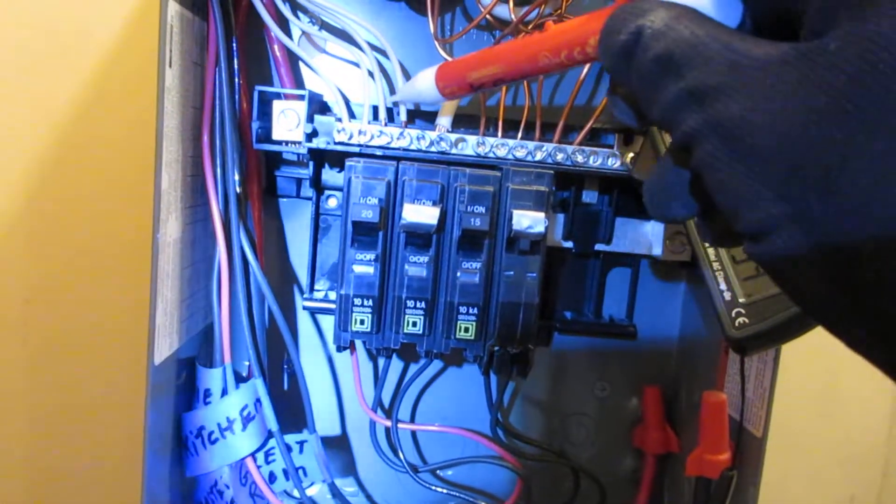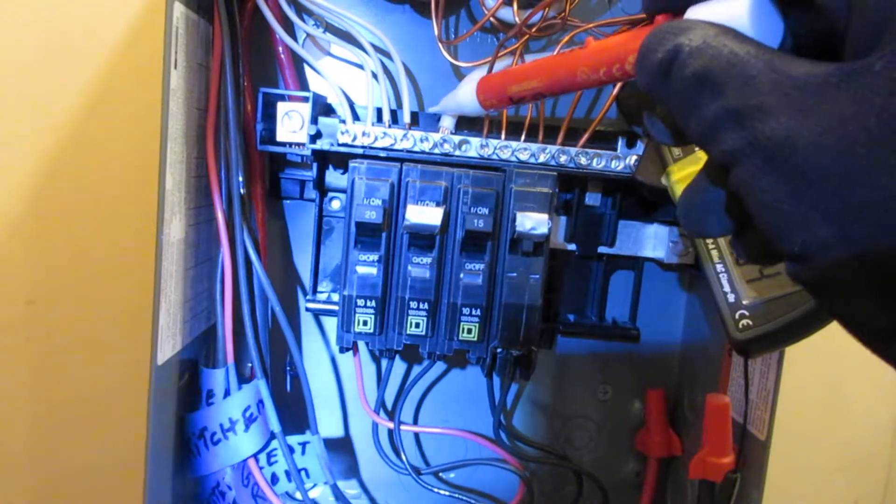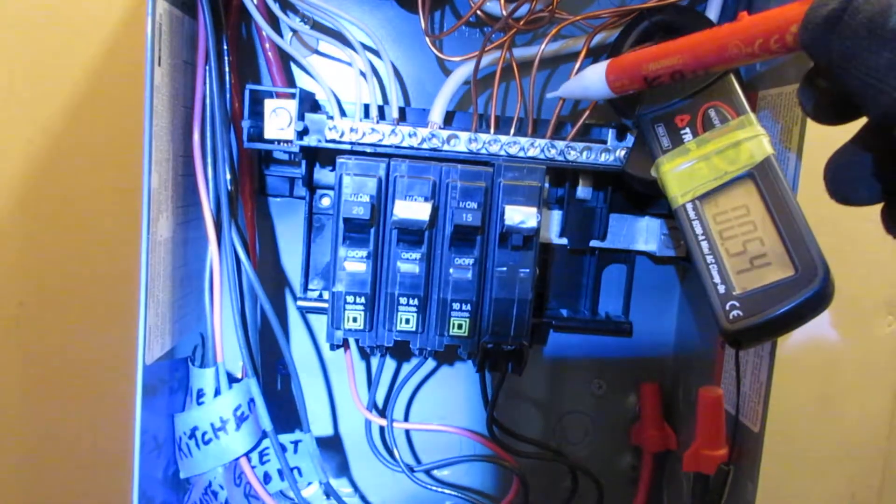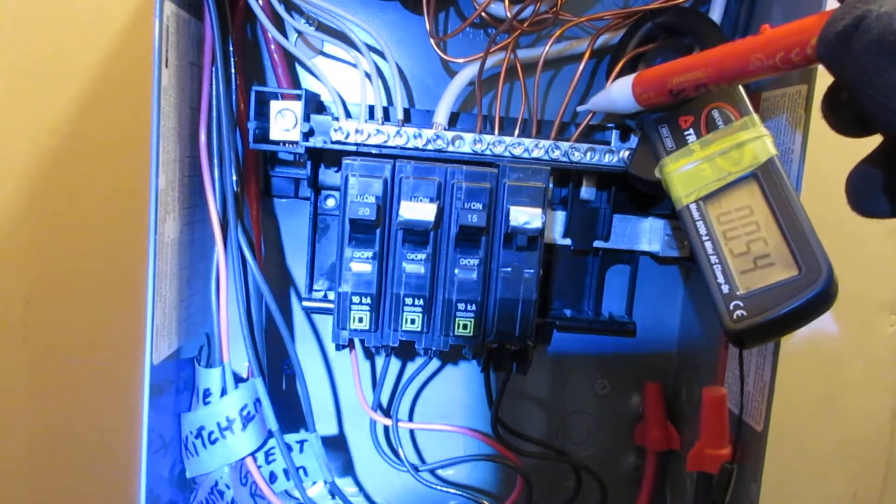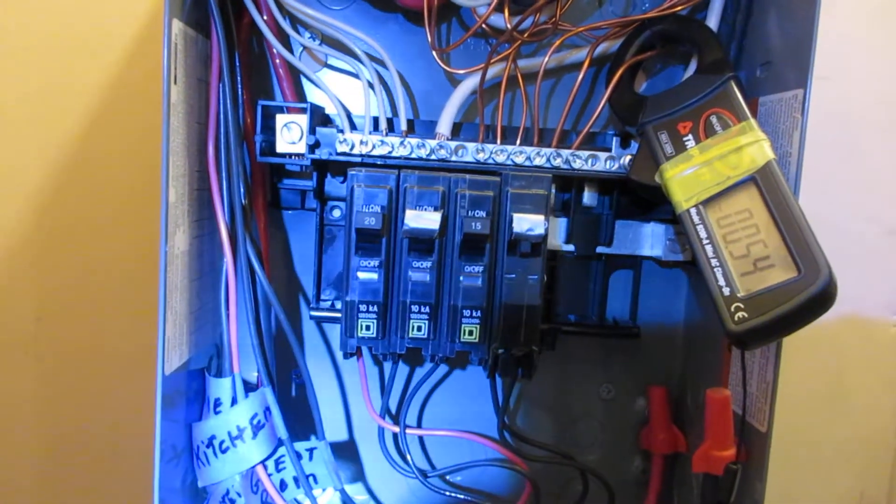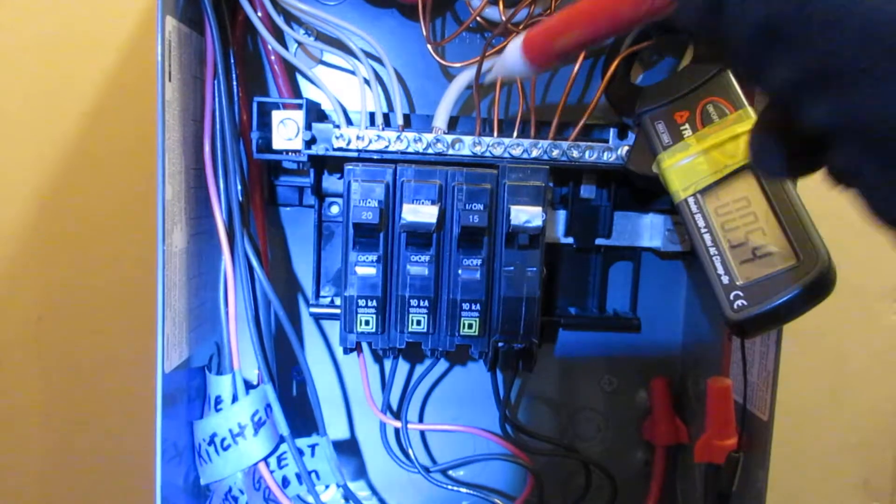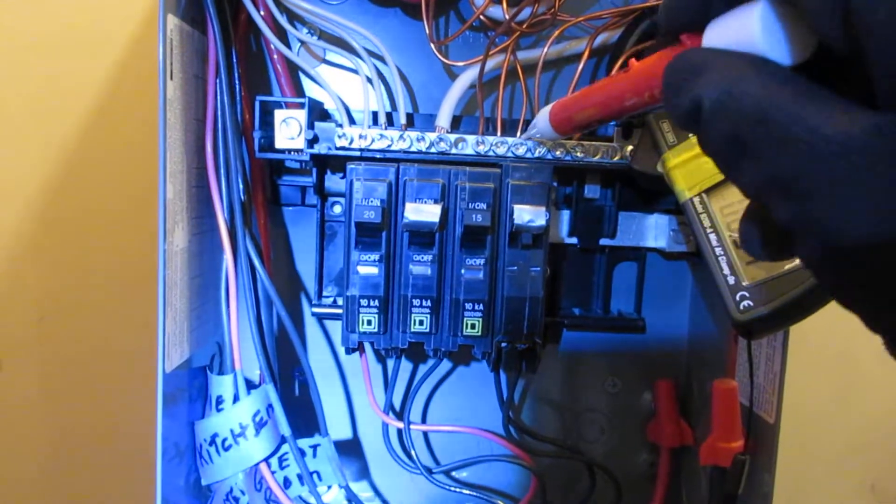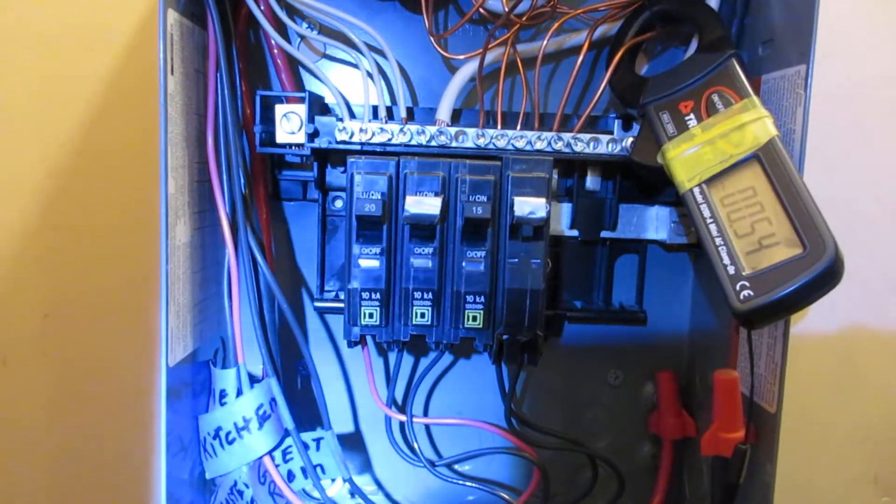Neutrals, which are whites, and grounds, which in this case are bare copper, are never ever to be connected to the same bus bar at a sub-panel.